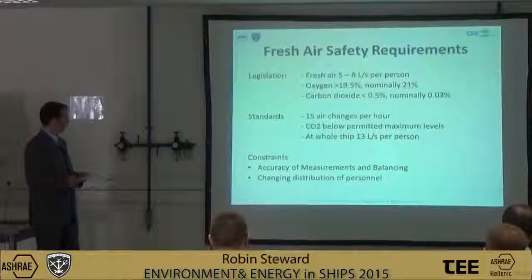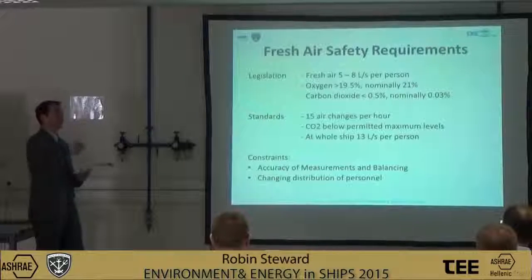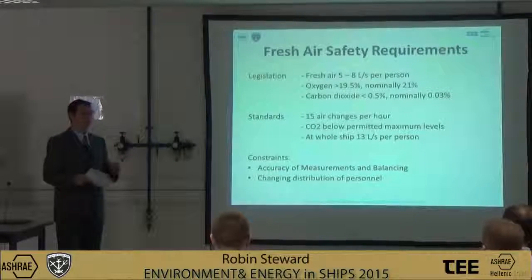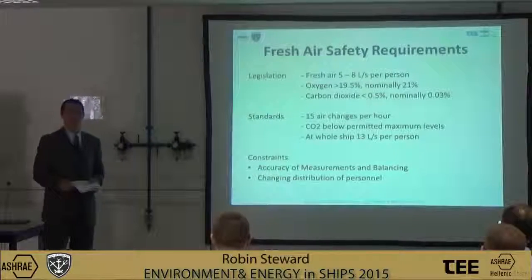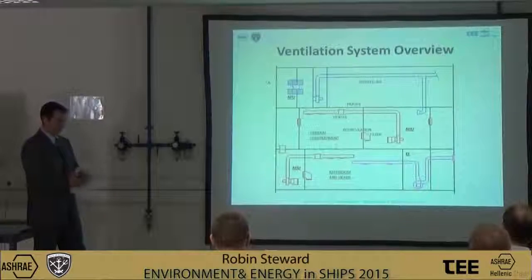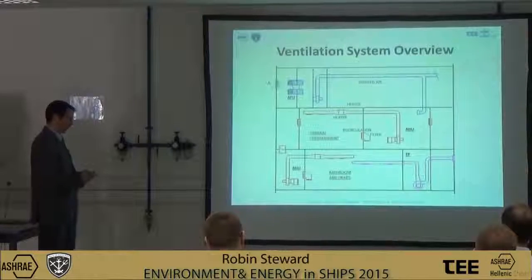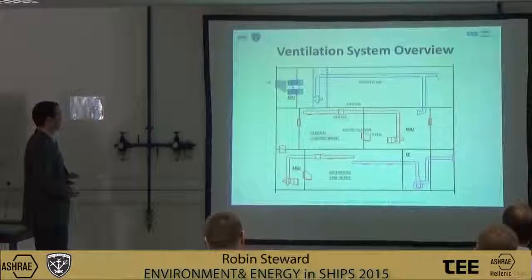The constraints encountered when measuring these ships include: readings taken with an anemometer at the ventilation grilles are not an indication of air quality — purely of airflow into the ship. Another problem is that modifications to compartments in lower deck areas mean that carbon dioxide, being heavy in air, naturally migrates to the bottom of the ship where personnel mess spaces are located. This layout is similar on all UK naval platforms and has become a traditional legacy rather than developing with modifications and advances in technology.